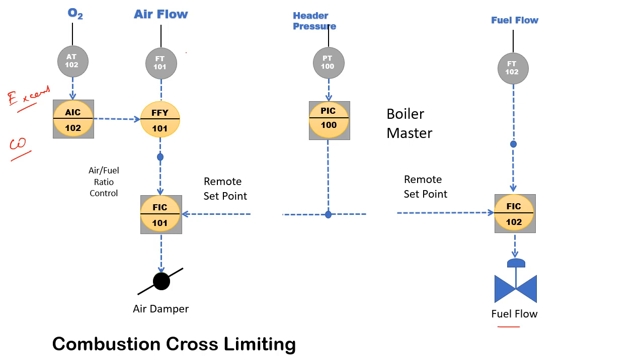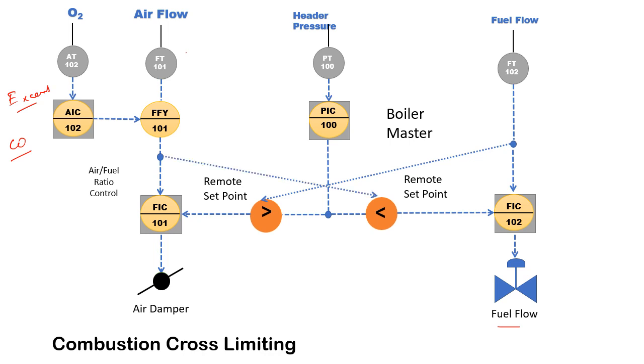To avoid the accumulation of fuel in the boiler or furnace, combustion cross-limiting is applied. A high selector is used, which takes input from both airflow and fuel flow, and whichever is higher gets fed into the air-fuel ratio controller. On the other hand, a low selector takes input from the airflow and fuel flow, and whichever is lower goes into the fuel controller, which regulates the fuel flow.